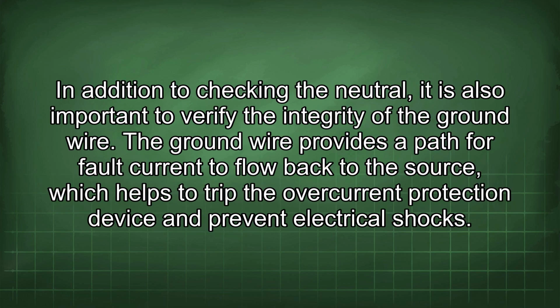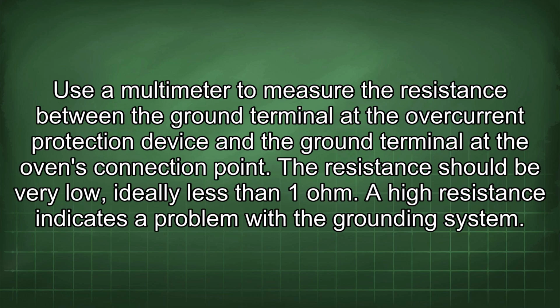In addition to checking the neutral, it is also important to verify the integrity of the ground wire. The ground wire provides a path for fault current to flow back to the source, which helps to trip the overcurrent protection device and prevent electrical shocks. Use a multimeter to measure the resistance between the ground terminal at the overcurrent protection device and the ground terminal at the oven's connection point. The resistance should be very low, ideally less than 1 ohm. A high resistance indicates a problem with the grounding system.